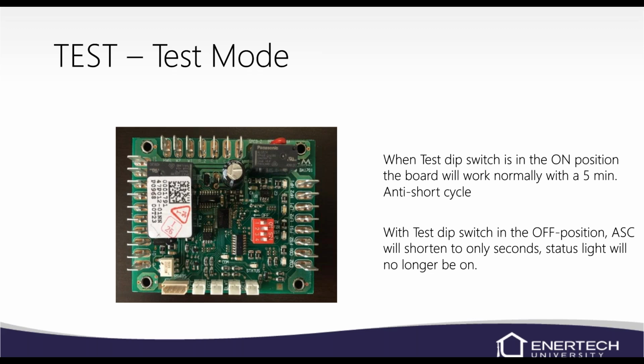You may make a note, to yourself or on your ticket, that, hey, I forgot to move that test jumper next time we're out there for service, to make sure to flip that back to the normal position. But it won't affect the unit, at least after that hour that it's been off. So don't really stress too much about it. We used to have a little jumper and people would pull it off and forget it or lose it. So that's why we did that, and we've just carried it over to the newer upgraded board.